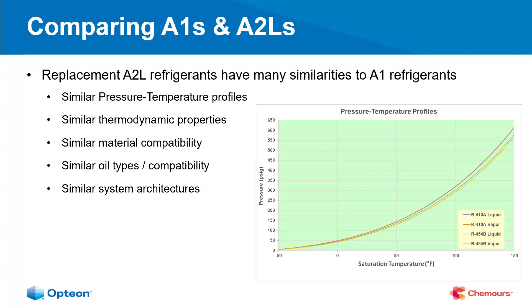This is great for the industry because it helps minimize system redesign. For example, comparing R-410A and R-454B, they have very similar P-T relationships and close capacities and efficiencies. R-454B, which looks to be the dominant replacement for R-410A for North America in air conditioning applications, is slightly lower in capacity, slightly higher in efficiency, has slightly lower operating pressures and slightly higher discharge temperatures — but overall the performance difference is not tremendous.